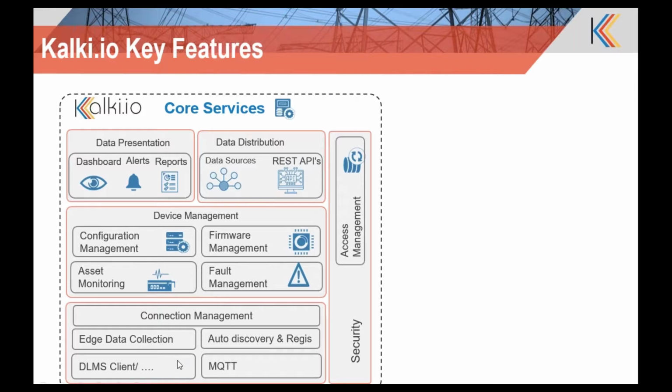And it also has the capability to connect with edge devices, where your meters are connected to edge devices over a last mile network, like PLC or RF, LPRF, or even a daisy chain RS-485 network. The edge device will collect data from these meters, and Kalki.io can collect data from these edge devices as well. And if you have another interface like MQTT or OPC UA, that can also be integrated with the Kalki.io metering headend.